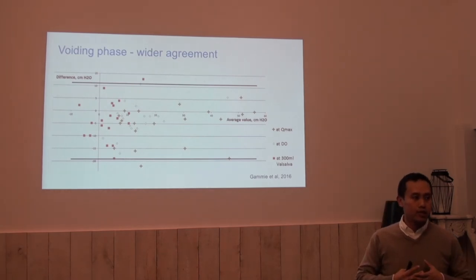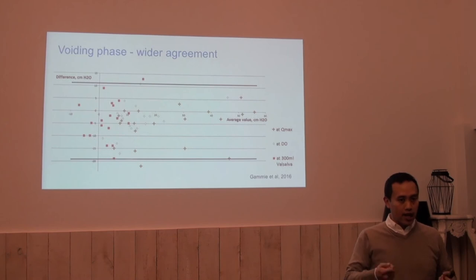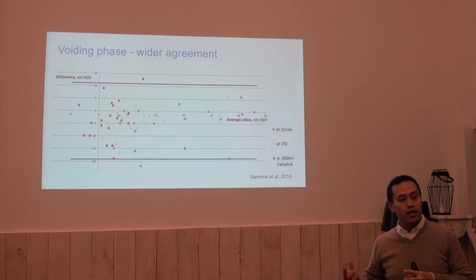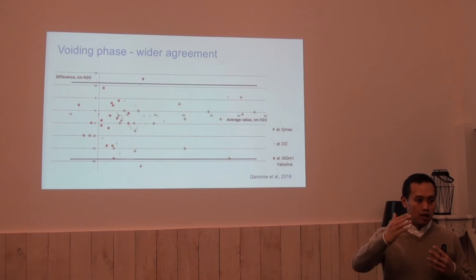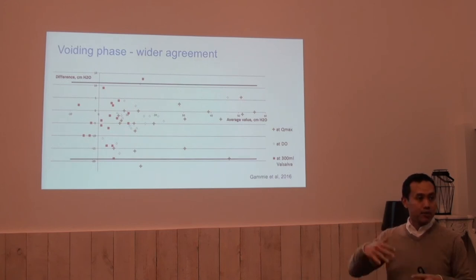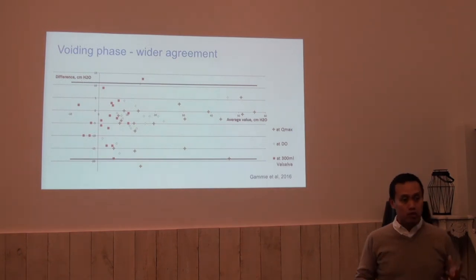What I take away from this is that the air charge catheter — when first inserted and then charged — even though we say it's zero atmosphere, will start with perhaps a random starting value. That random starting value is corrected at the beginning. However, that still shows we have a large spread — something else in addition to that.